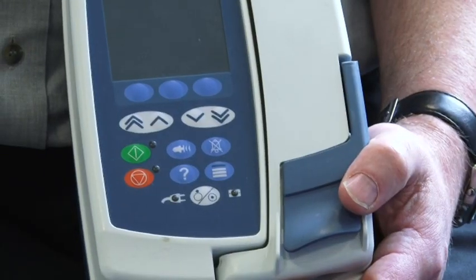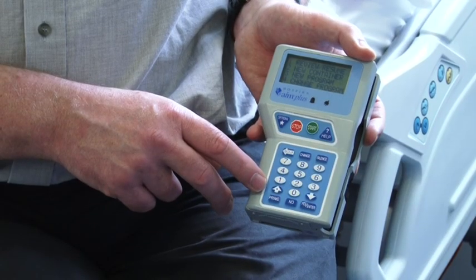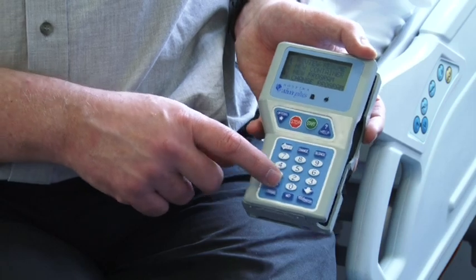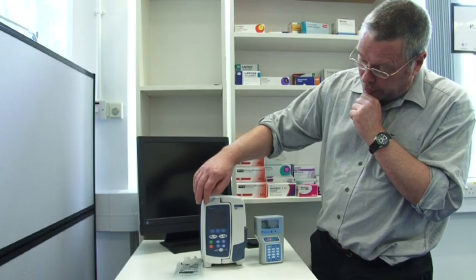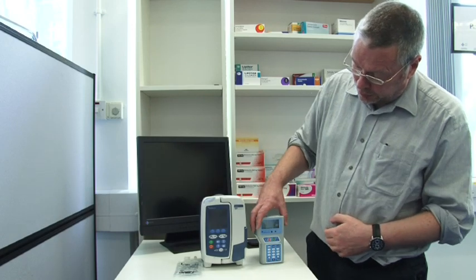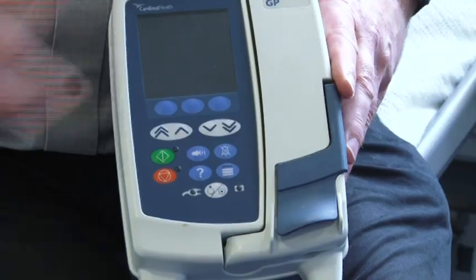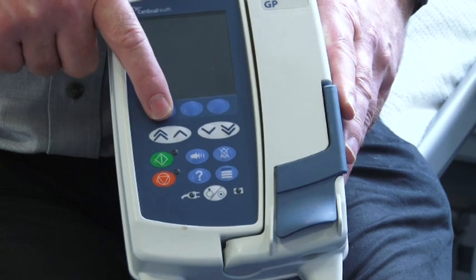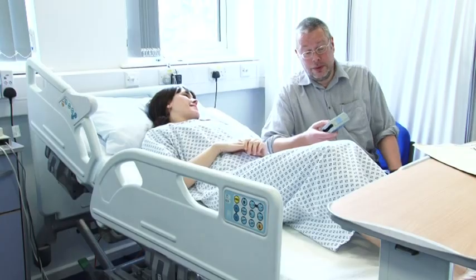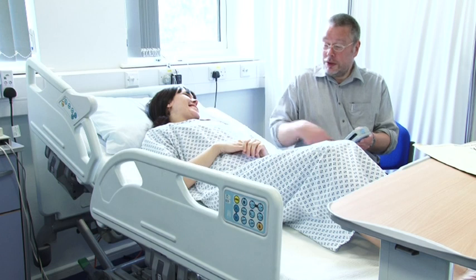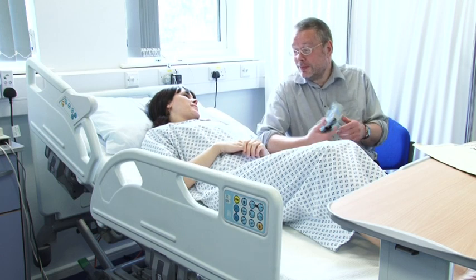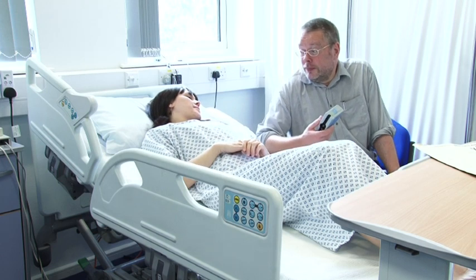So one sort of infusion pump has up-down keys to increase or decrease a number. The other has a keypad with ten digits and a decimal point, and you type in the number you want. Which is better? We've done experiments, and it turns out the up-down keypad is twice as good. The reason is, with a numeric keypad, when entering a number like 12.3, you just press the keys.